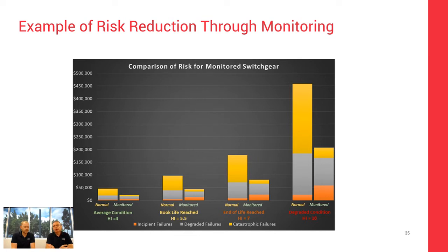The statistics would indicate that roughly 8 in 10, so 80 to 85% of failures are associated with partial discharge activity. So there will be a proportion of failures that don't occur, but if you're going to do one thing and one thing alone for switchgear or for cables, then partial discharge is the one that will get you the most of those failures and reduce that. But as we're showing in this graph here, there will be some that would be left behind and not detected.